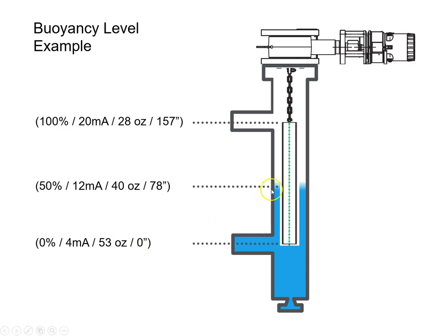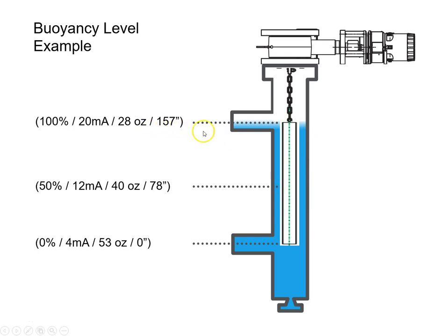At 50% level, or 12 milliamps, we'll measure 40 ounces or 78 inches. We can see the liquid level is actually rising, so it's providing more buoyant force to make the displacer appear lighter. And finally, when we get to the upper range value — 100%, 20 milliamps — we see 28 ounces or 157 inches. The liquid is providing more buoyant force to the displacer, so it's at its lightest here.